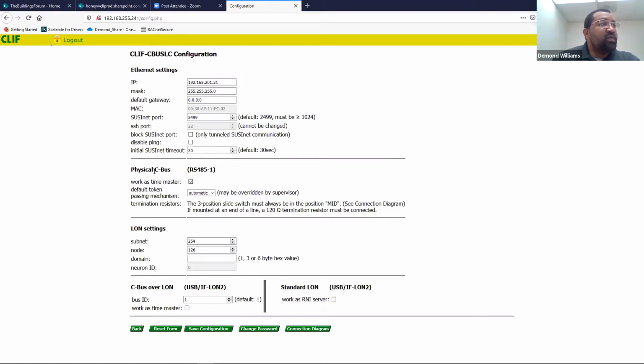So we're going to be working with a physical C-bus, which is actually going to connect to the RS-485 port on the controller itself. The controller can actually do C-bus over LON. What C-bus over LON is, is that the controllers were set up as LON, and they were pulled into an iLON 600 router to make it Ethernet, and then Honeywell goes into their C-bus configuration and sets that up, which they are calling a virtual C-bus.